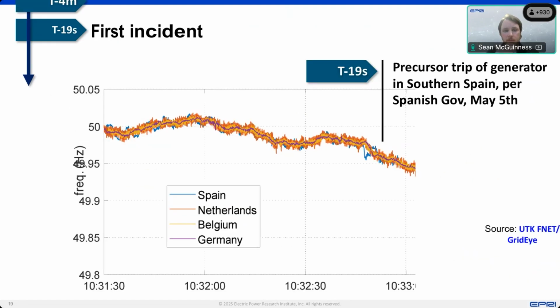Then moving into really close into the seconds. So we've moved from minutes prior to the event into seconds beforehand. So initially after the event, the blackout occurred, there was a lot of discussions around 2 generators tripping and the consequences of those. In recent days, the Spanish government came out and said there was actually a 3rd tripping, and it began 19 seconds before the blackout. So you can see this little slight dip in frequency, and this was actually a generator that tripped.